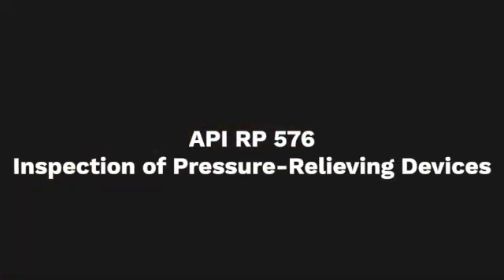When we go out and either as part of a compliance audit or we're doing just a mechanical integrity specific gap assessment, when we look at relief systems, we compare the company and the site practices to the applicable RAGAGEP. The key applicable RAGAGEP for a relief valve inspection, testing, and maintenance is API Recommended Practice 576. So we look at the should and shall expectations in that guidance document when we're auditing or assessing an owner-user.